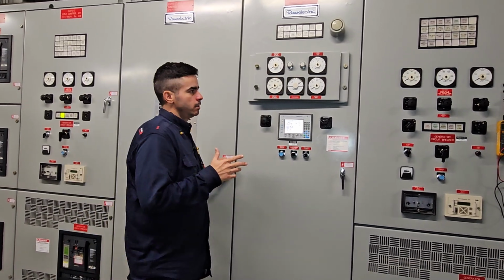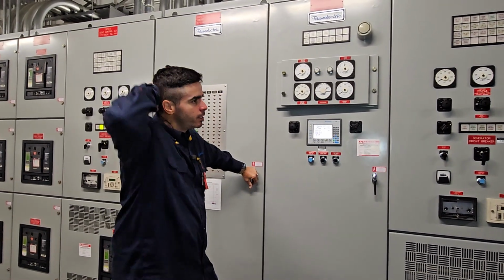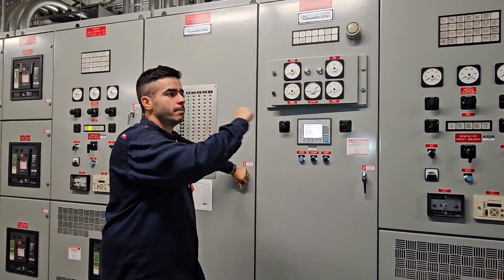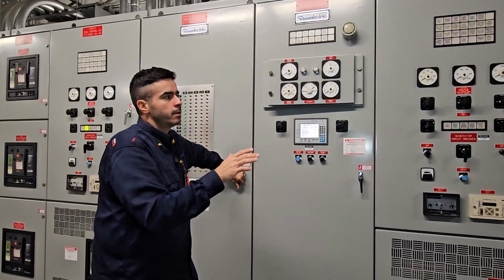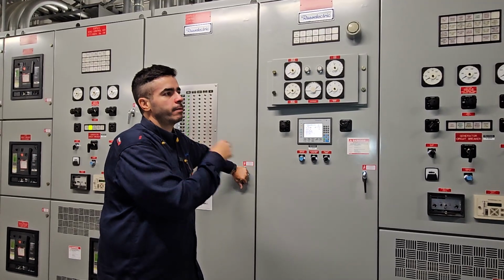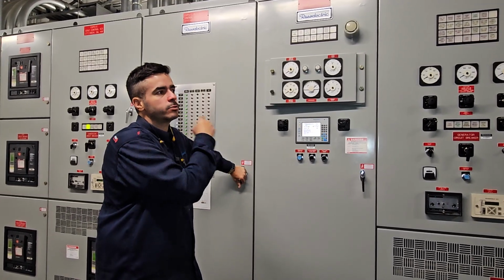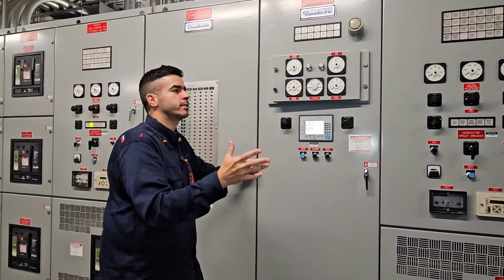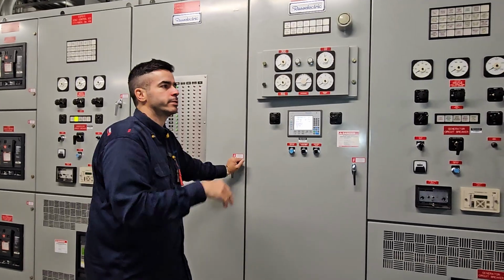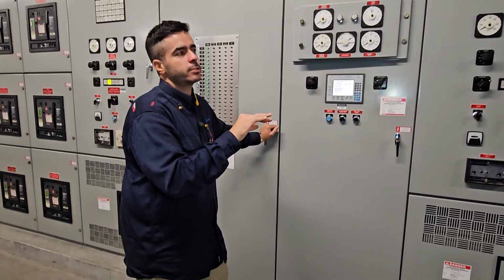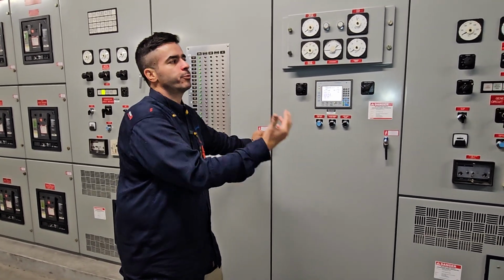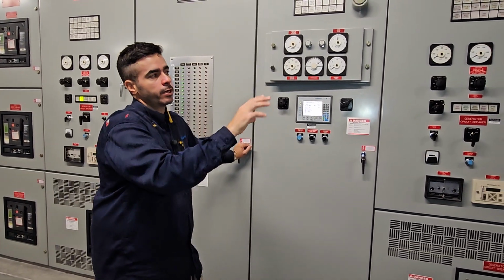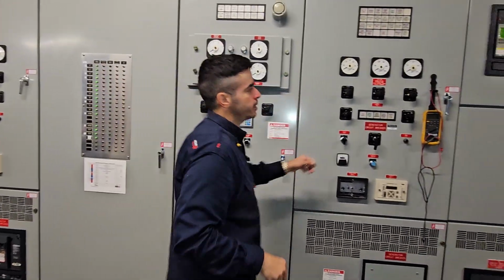All right. So what I want to do now, Lalo, is run the gens. I want you guys to see how I do the setup after the PM. I have to do that because I haven't done it since the PM, and in order to get it all together, I have to make sure the parameters are set well. But I figured it was a good idea to do it while you guys are here. What I'm going to do right now is something you usually don't have to do, because I'm going to put my meter on the back of the voltmeters, but I'll be explaining what I'm doing, okay? I'm going to start with this gen over here.